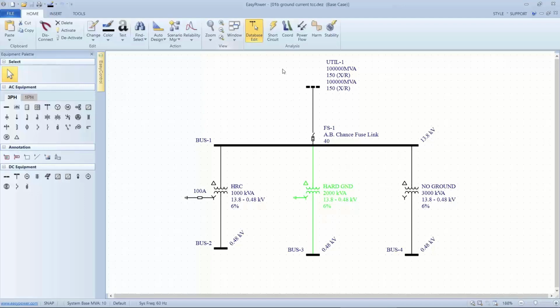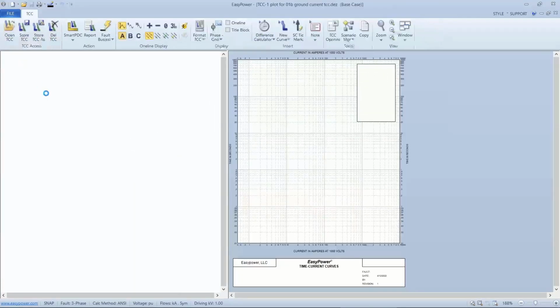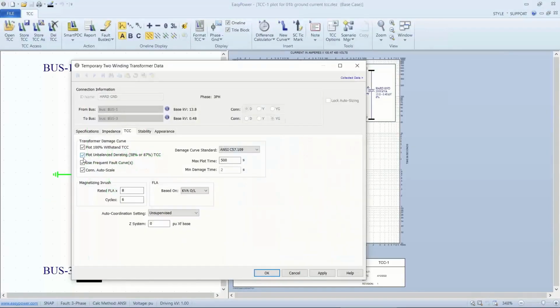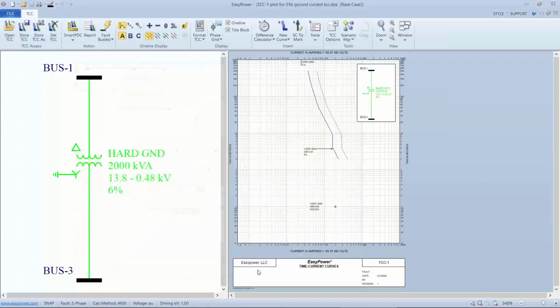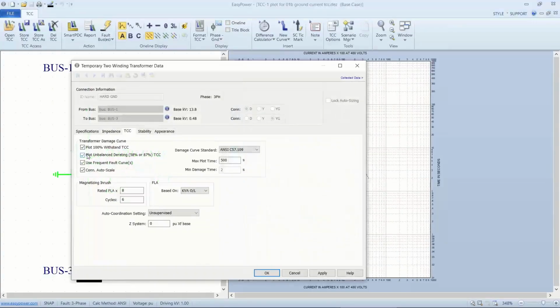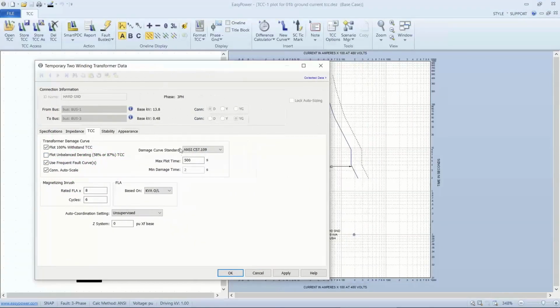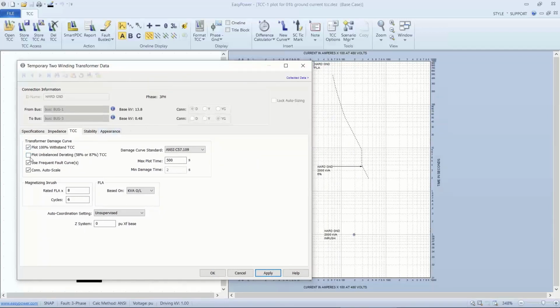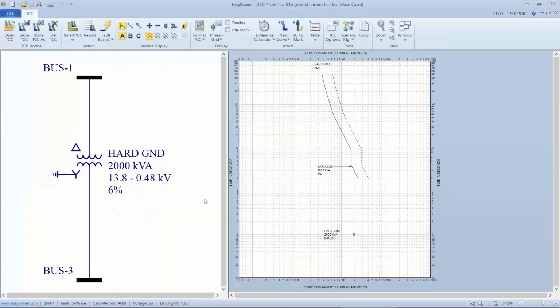Probably should have done a delta delta because they're similar. All right, so let's look at the hard ground first. What we see when we look at the parameters is that we've checked this box, which says plot the unbalanced derating of 58% for the TCC, and that's given us this jag in the current. Let me uncheck it and see what it looks like. Again, it takes away that part of the curve. Now, what does it hurt? Well, it doesn't hurt anything as long as we're trying to coordinate for three-phase faults. But as soon as we look at a single-phase fault or a line-to-ground fault, then that 847 amps isn't compared.